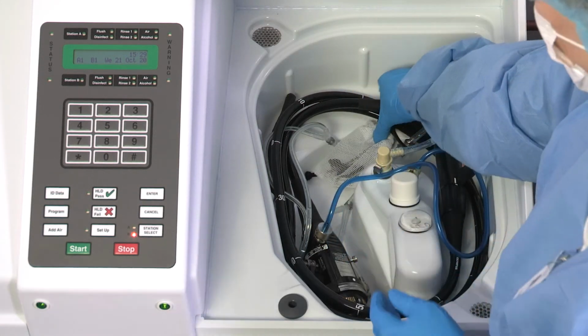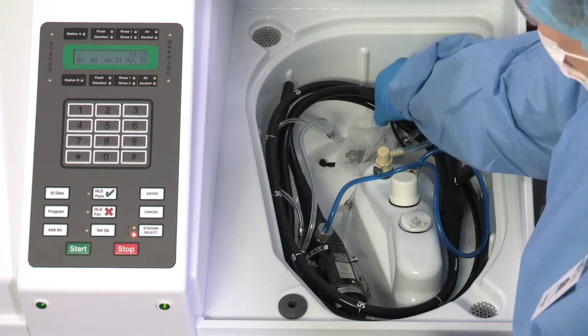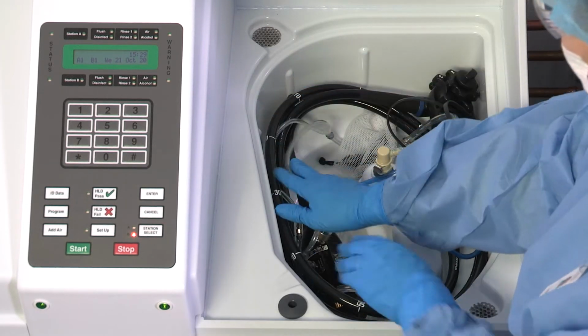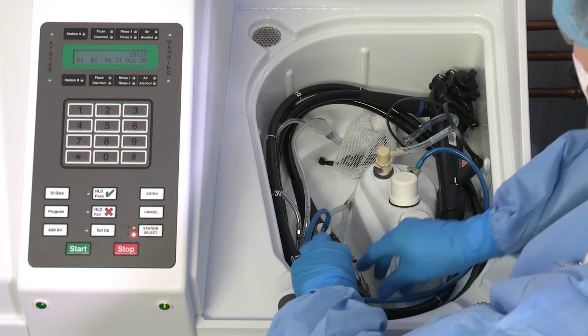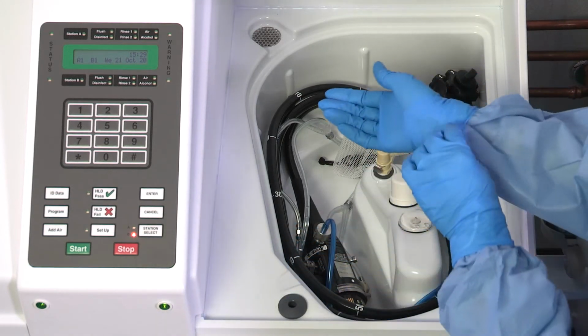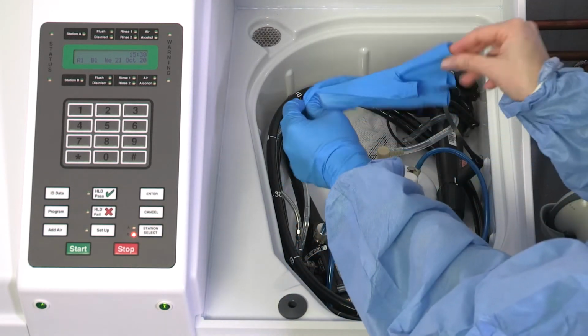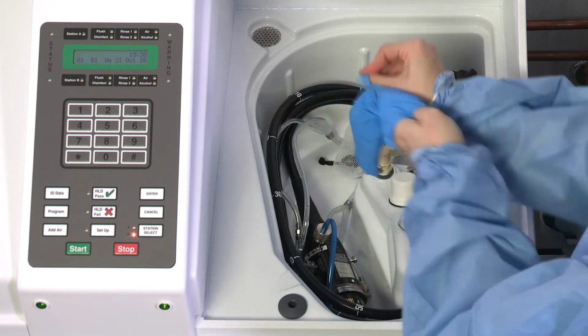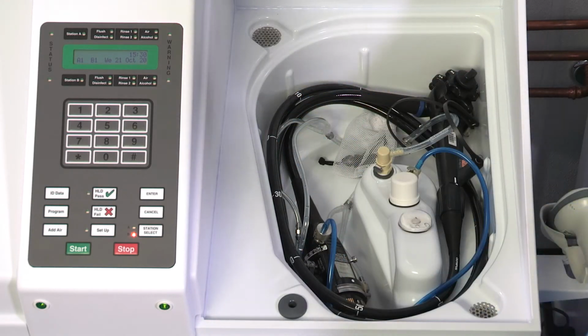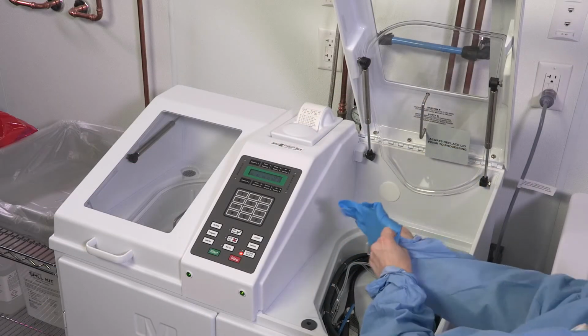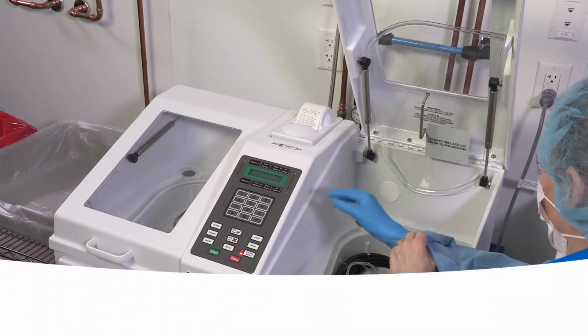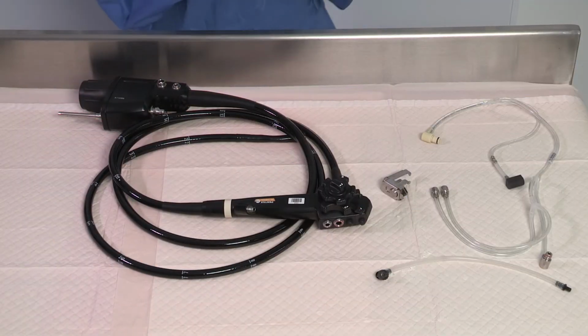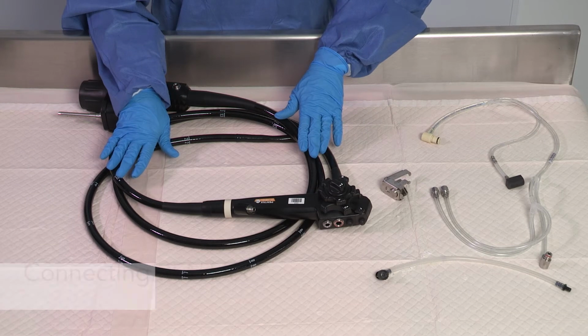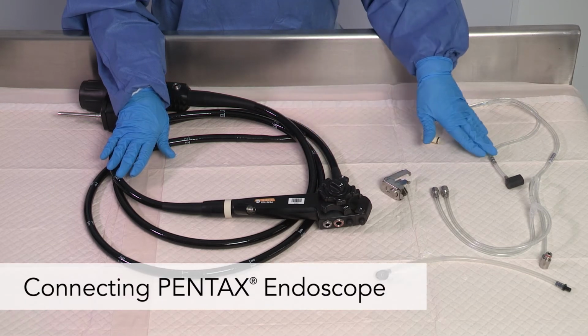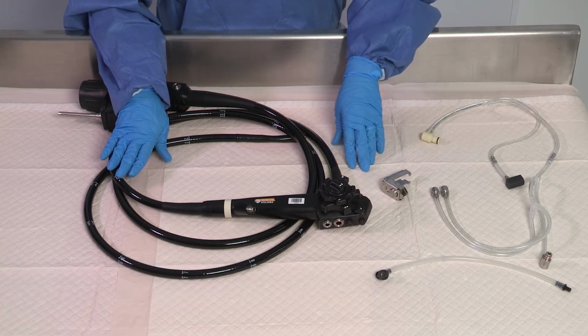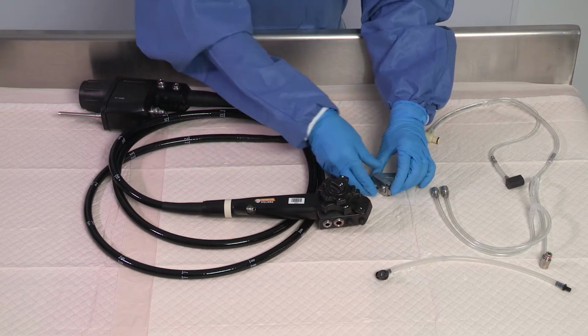Place the accessory bag in the basin and tuck it underneath the endoscope to prevent floating. Do not reprocess water bottles or forceps in the DSD EDGE Reprocessor. Once the endoscope is secured in the basin and properly connected, remove contaminated gloves and replace with clean gloves. Let's review how to connect a Pentax endoscope with a forward water jet. Refer to the manual to ensure correct placement of the connectors.